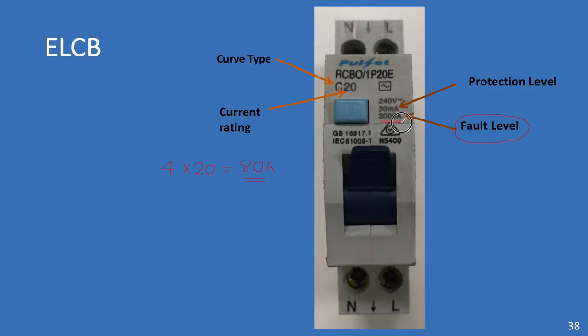So, quite often you'll do the fault loop impedance checks, and it can often well exceed our 80 amps, but if it also exceeds 3000, then you're going to have trouble with this circuit breaker. This circuit breaker is not going to be able to electrically and mechanically withstand a fault current greater than 3000 amps for one second.